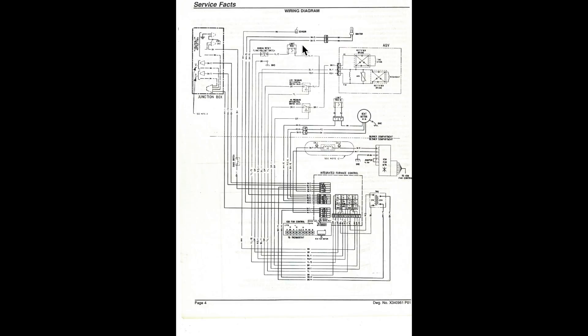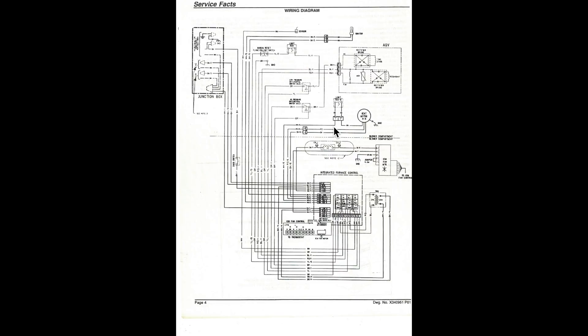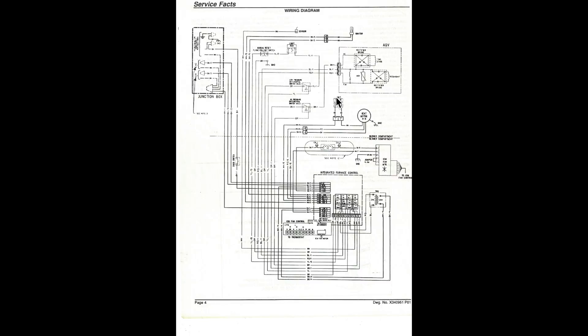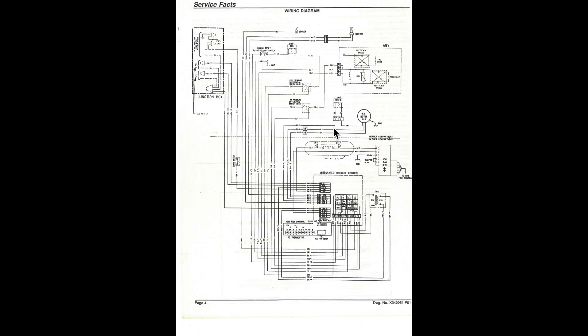And this one here is going to be the limit that shuts it down if the temperature of the air passing by the heat exchanger gets too high. There's another one down here that's actually located on the vent motor. If the air coming out of the vent motor gets too hot, it'll shut it off.